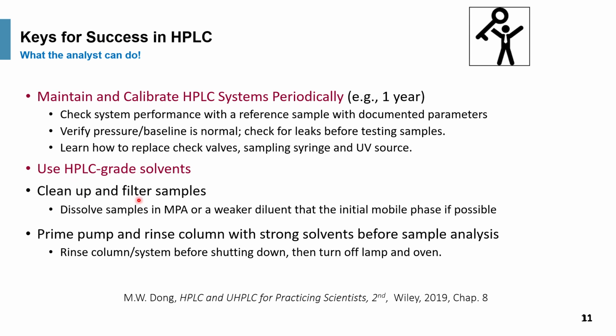Always use HPLC grade solvent, clean up and filter the sample, and make sure that your sample diluent is weak, if possible. A weaker diluent would prevent any anomalies from distortion from an injection of a stronger diluent.